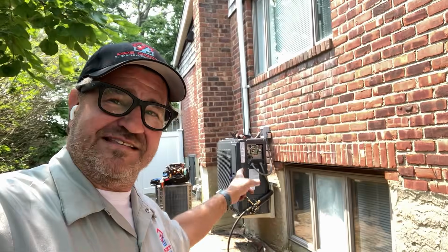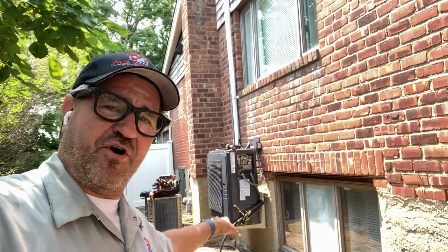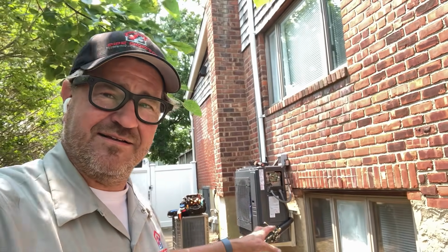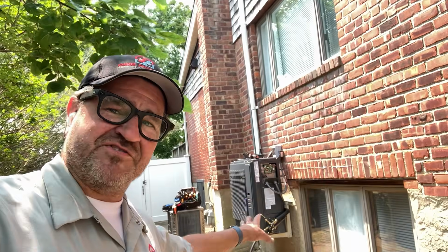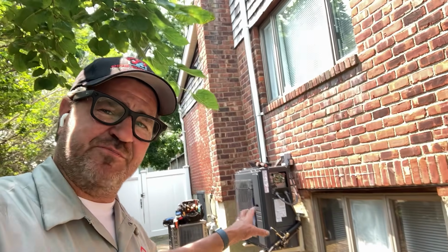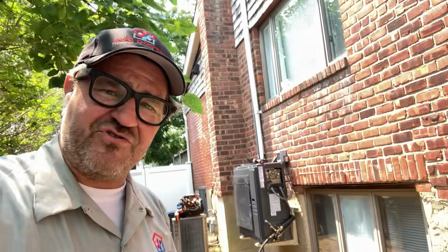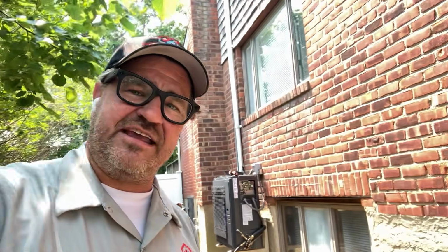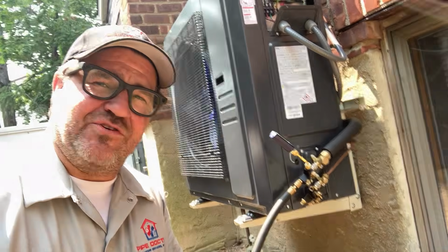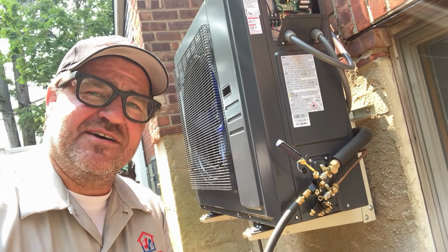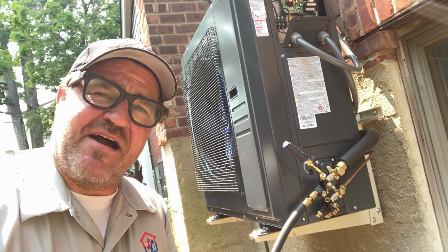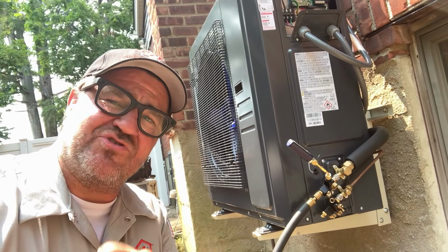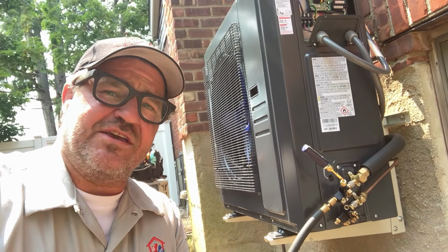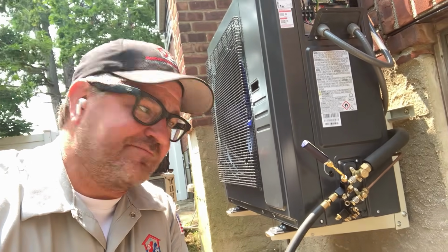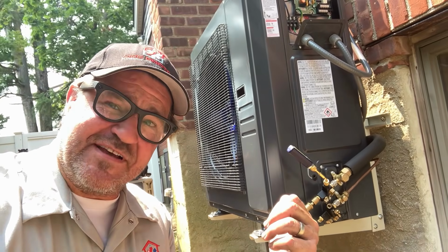That inverter-driven compressor is the most expensive part of the entire system, right? Remember, inverter-driven compressors like this one, the ACiQ Extreme Plus system, are precision machines. They deserve a clean, dry refrigeration circuit from day one. A proper vacuum isn't about checking a box on an install checklist, right? It's about giving your customer the best possible chance of getting 15, 20 years or more out of their investment. And you best believe this is a sizable investment.